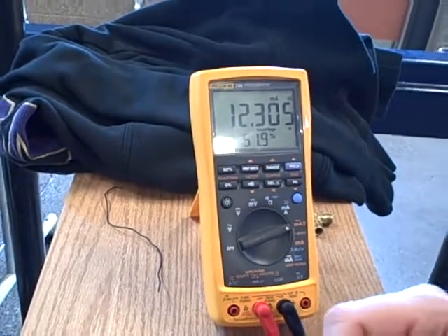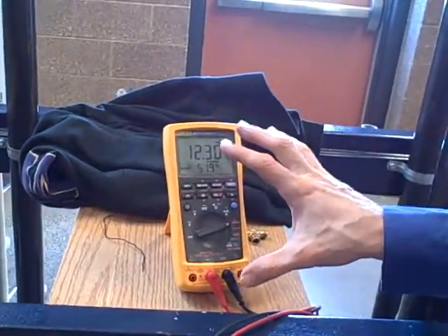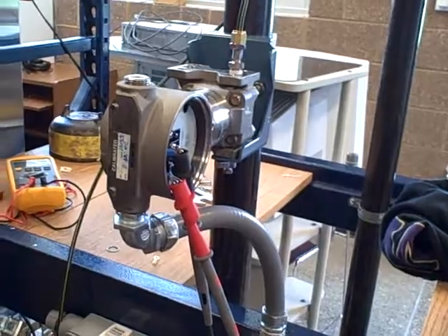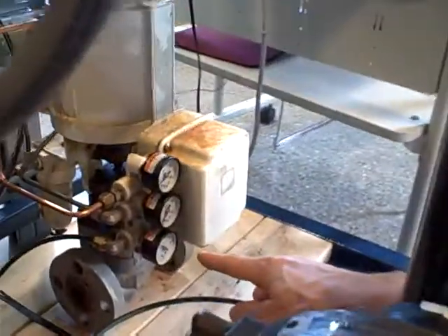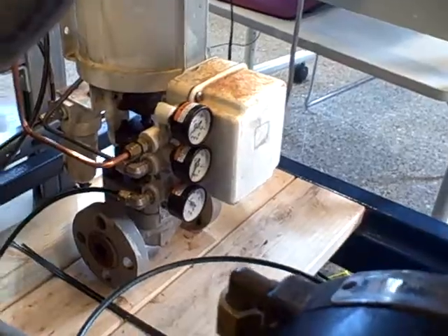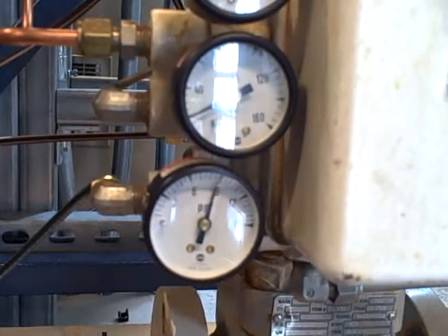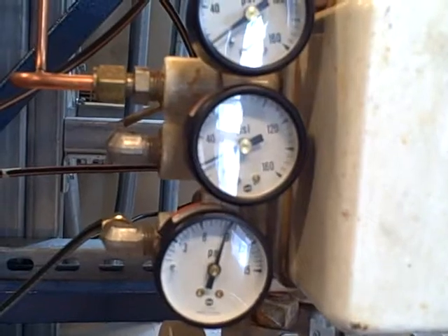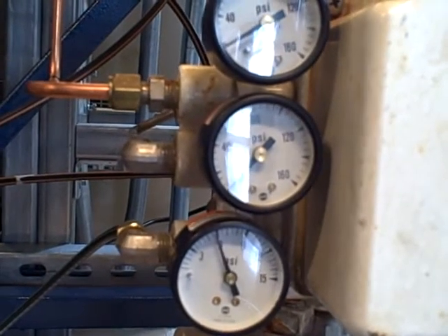Now, one thing else I want to show while we've got this hooked up, we are simulating a signal to the transmitter. Our controller happens to be in automatic mode, and it's controlling the position of that valve. If we take a look at this pressure gauge down here in the positioner, that is the signal coming from our I to P converter, currently a little over 3 psi. As I move the signal on my Fluke Model 789 process meter, you're going to see that signal march up. There we go. Then I'm going to go down on my current signal, and you're going to see it going down.